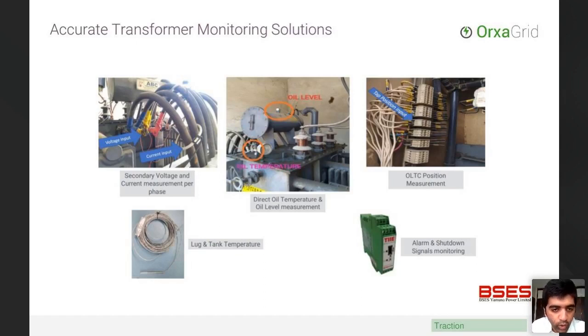Moving on to oil level and oil temperature, the photo is not too clear, but you can see we do direct installation of our sensors, to get the most reliable and accurate readings. For oil level, we install it in the cap of the conservator tank, the same input point where the oil is filled. If an oil replacement is required, we just remove the oil level sensor, refill the oil, and then put the sensor back on, just like a cap.